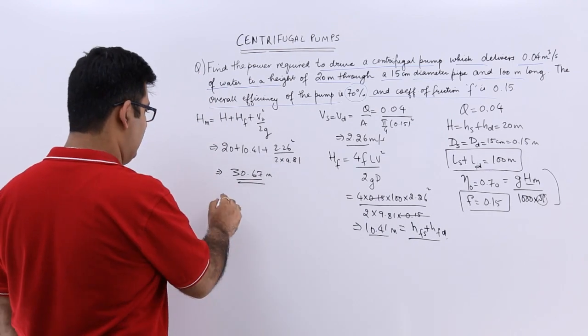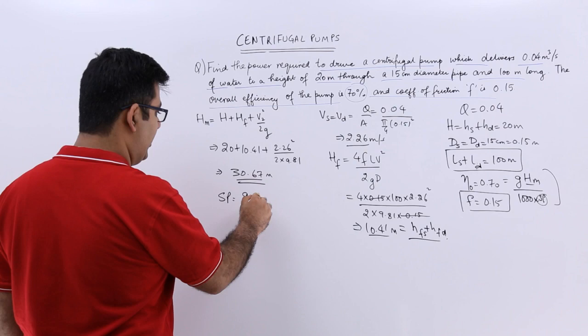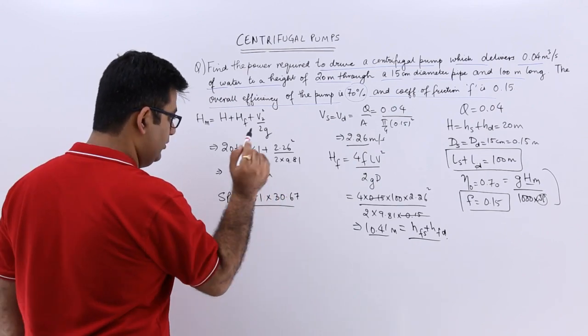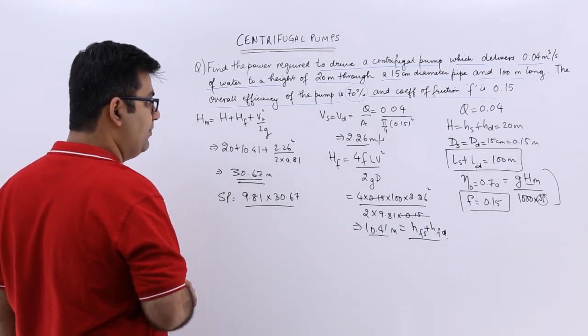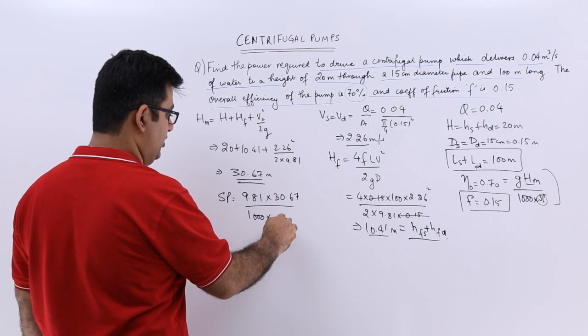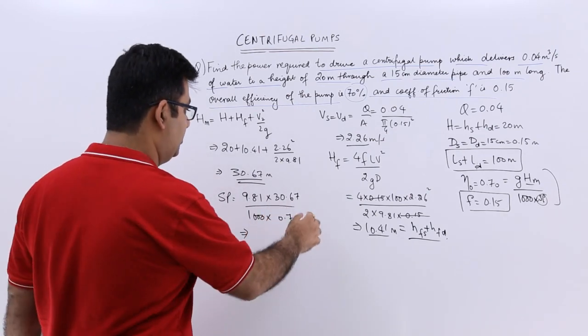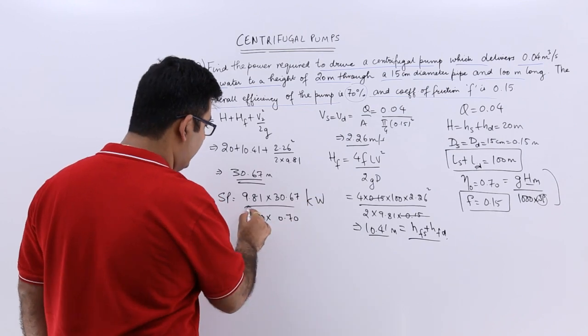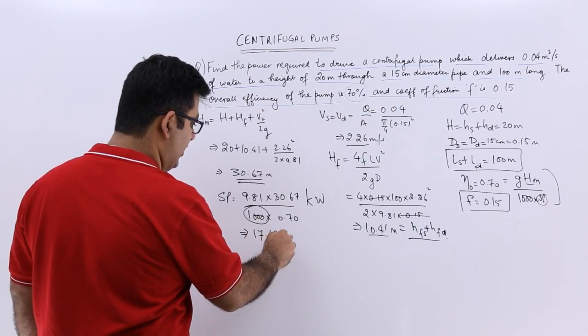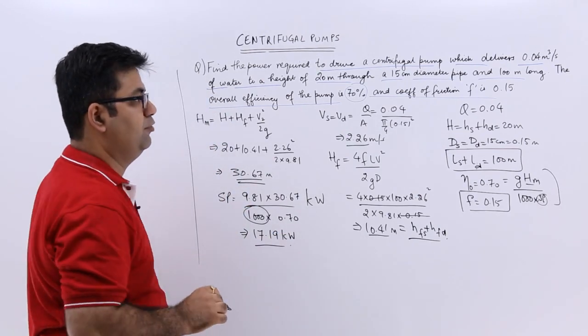Now applying the formula, the shaft power = (9.81 × Q × H_M) / (1000 × eta_O) = (9.81 × 0.04 × 30.67) / (1000 × 0.7). Because we are already dividing by 1000, this gives the shaft power in kilowatts, which comes out to approximately 17.19 kilowatts.